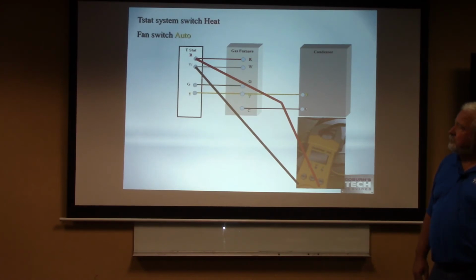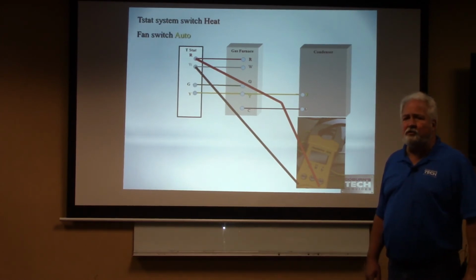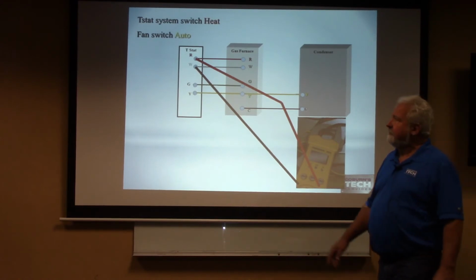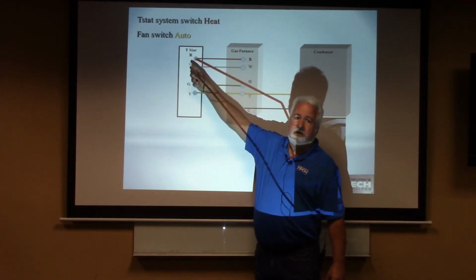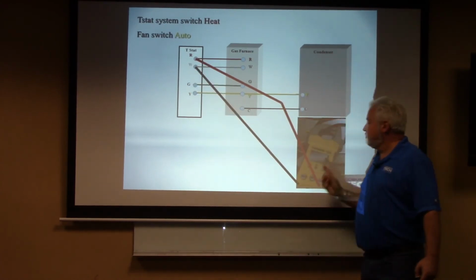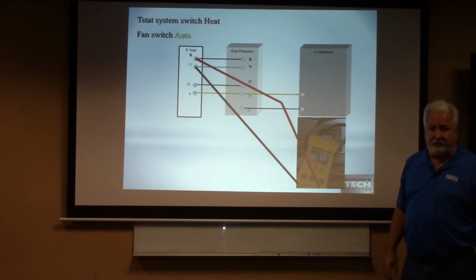You're in the heating mode. What should I read across R and W? If I'm in the heating mode, it's in the auto. R and W. You with me? What do I read across a closed switch? In the heating mode, is the R and W closed? R and W is closed. I should read 0 volts. Everybody okay with that? Good.